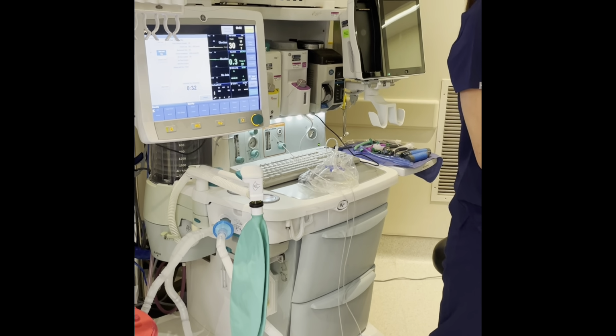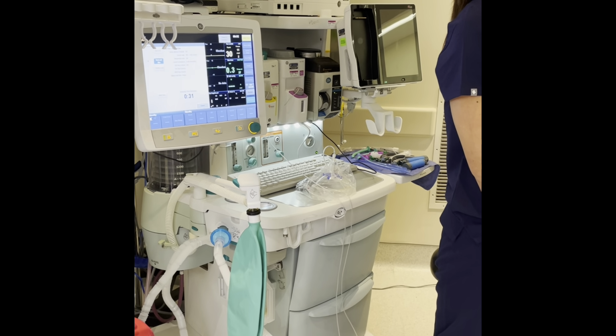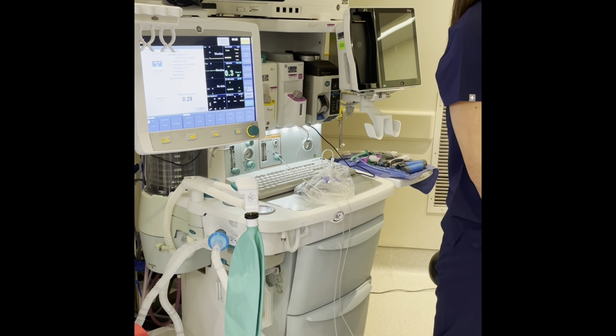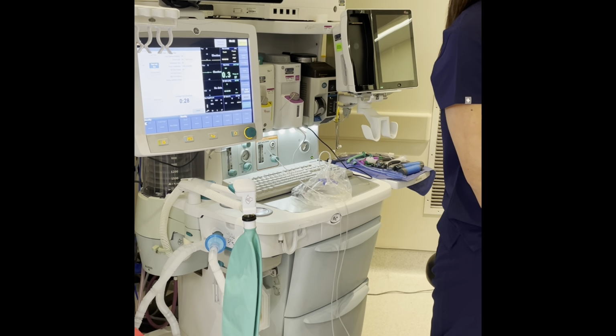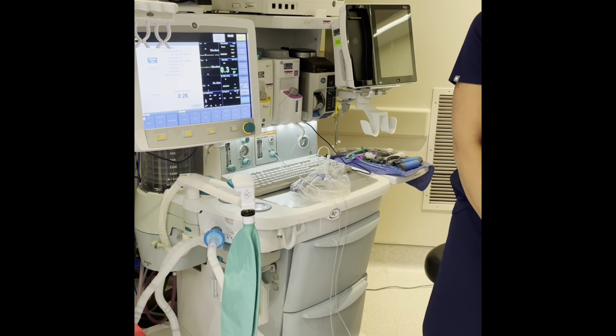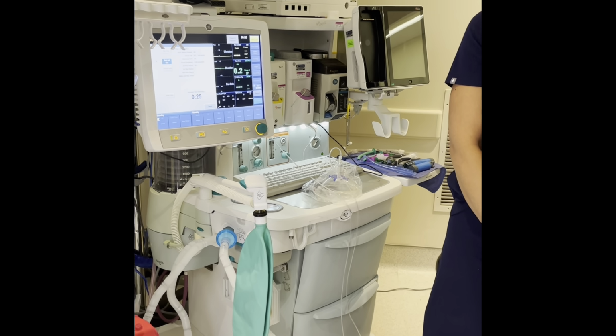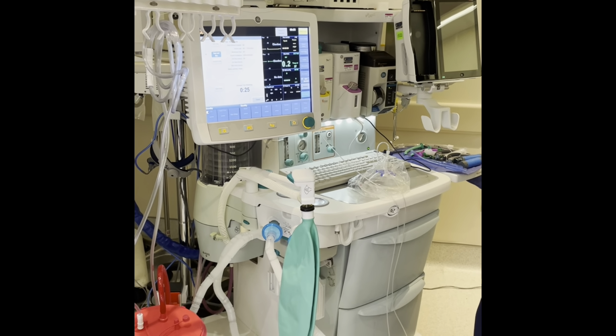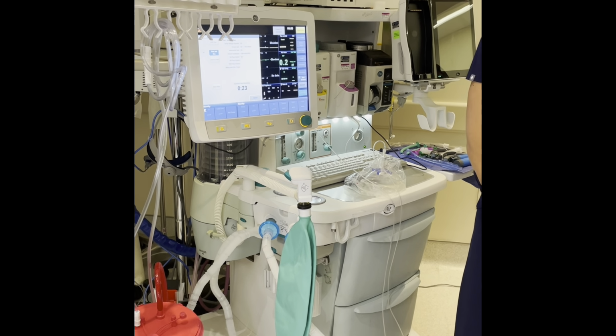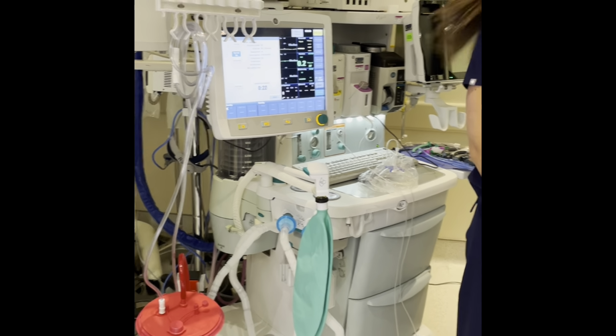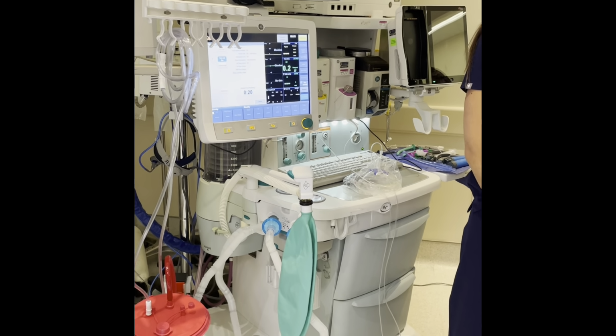We'll show you on this machine, there's a circuit test that you have to do in between each case. You can do it automatically, and there's a way to do it manually as well for machines that don't have the automatic check. Right now, which part of the machine is it checking? On the older machines, you would be doing this manually. But thank goodness for the new machine, it does it on its own.